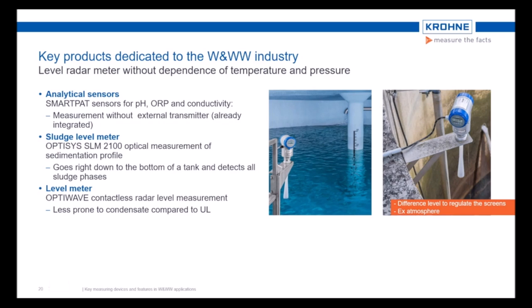Furthermore, operators will make use of additional advantages such as its independence of pressure or temperature due to the electromagnetic wave which is used. Ultrasonics use an acoustic wave which needs to be compensated. Obviously this is often not realized. For example, when sunlight is heating up the converter housing, in which the temperature compensation is also installed, we see huge deviations because the temperature in the manhole where the level is to be measured is completely different. So radar is not sensitive to that phenomenon and therefore, of course, more accurate.